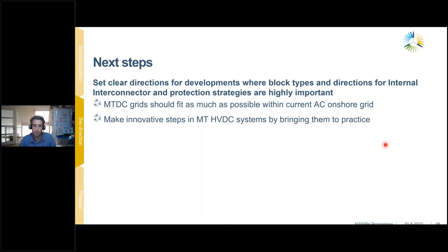We shouldn't forget usage is key. We've used this onshore AC grid already for decades, and this multi-terminal DC grid should fit in as much as possible. One example is the maximum loss of load or maximum loss of generation allowed by countries. For example, Denmark currently 700 megawatts, the Netherlands about 1,000 megawatts. Those bipolar converters, a bipole of 700 megawatts and a bipole of 1,000 megawatts, should all work together in a single multi-terminal DC grid.